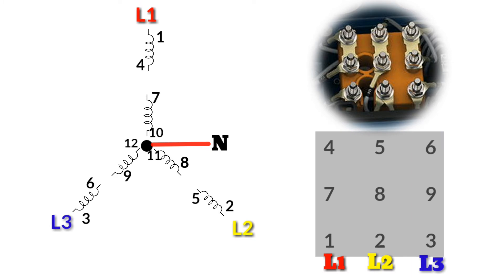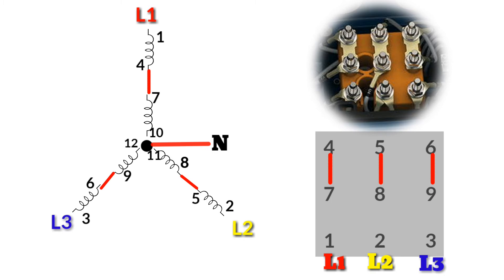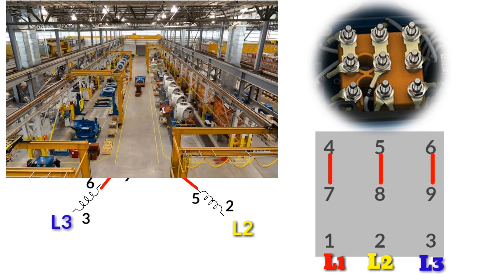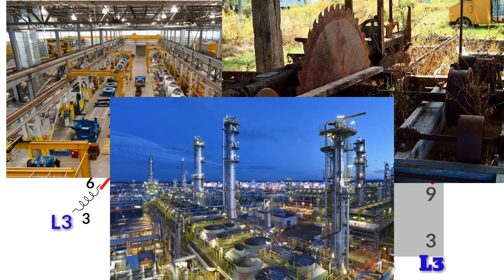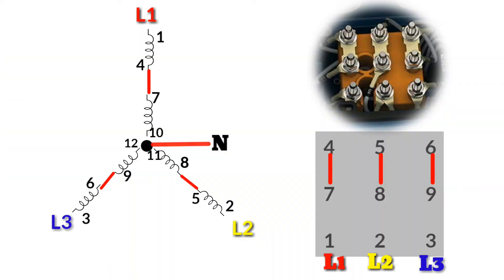To make the star connection, connect terminal number 4 and number 7, number 5 and number 8, number 6 and number 9. This type of motor connection is probably the most commonly used in factories, lumber mills, and other commercial plants. They are dual voltage and can be wired for either 240 volts or 480 volts. Each motor will have 9 numbered leads coming out of it, numbered to help the electrician identify the wire when connecting the motor.